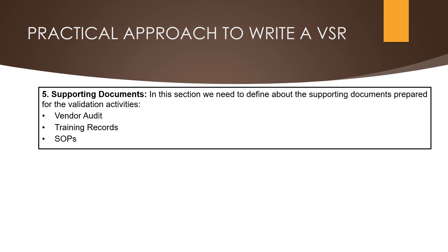The fifth component of the validation summary report is the supporting documents section. Here we need to define about the supporting documents prepared for the validation activities. For example, details of the vendor audit report — that is audit performed date, report approval date, any observations during the audit, action taken, and a conclusion statement. Next is training records — here we need to define about the personnel involved in the whole validation activities, such as creation, execution, review, and approval of validation documents, and that those personnel are trained.